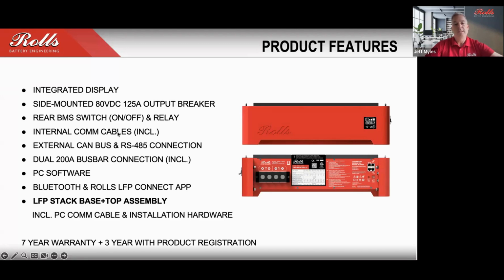The units have been designed with all of the connections on the rear of the unit. So you're going to have dual busbar connections for positive and negative. You're also going to have an RS-485 connection port and a CAN port. And then you're going to have a link in and link out port, which allow communication from each battery in the stack. The batteries will also have a screen on the front, which is going to provide you with state of charge information, temperature, current, and status. So you'll see whether or not the battery is in run, you'll see whether or not it's charging or discharging, and also any error indications, and that will be directly on the front.